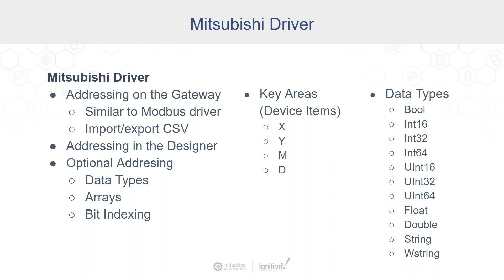The driver supports most device and data types. For Mitsubishi, these are usually prefixed with X for inputs, Y for outputs, M for internal relays, and D for data registers. Addressing can also span over multiple registers to handle larger data types, and also supports addressing arrays and bit indexing.